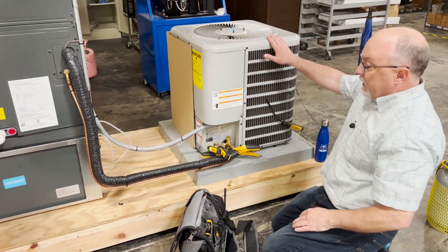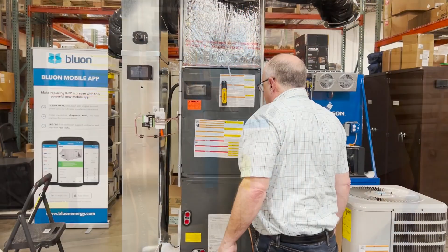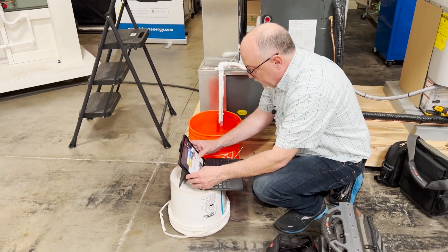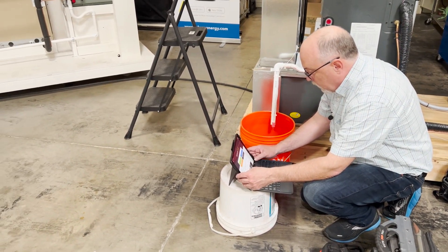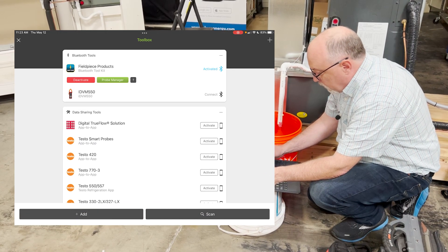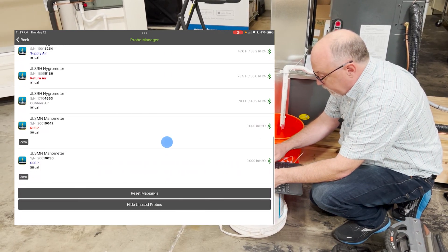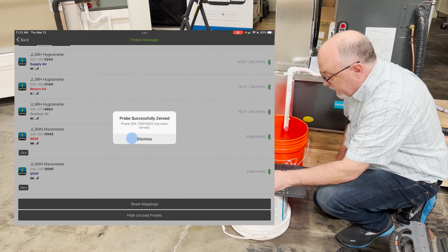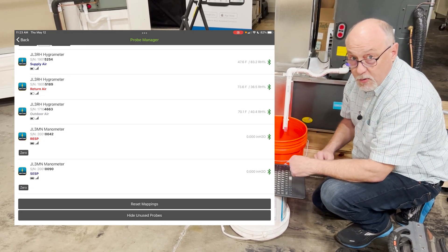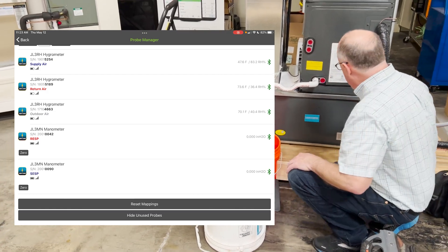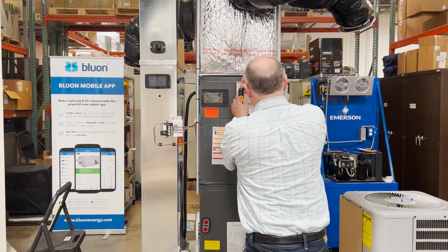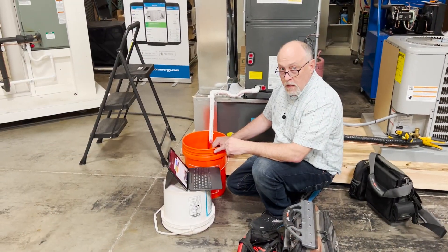Now we're just going to wait a second for that to stabilize. Let's go down to the tablet. I'm going to go ahead and turn on screen record so we can use this in the video. I'll hit the hot key, click on the toolbox, go into the probe manager, and then I'm going to make sure I zero my return air static — just go ahead and zero it again even though they're showing zero. The probes do drift over time, especially on the static pressure side. I'll attach these back up so we've got a static pressure reading.